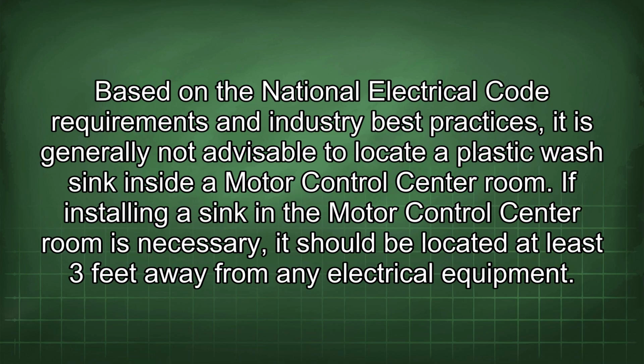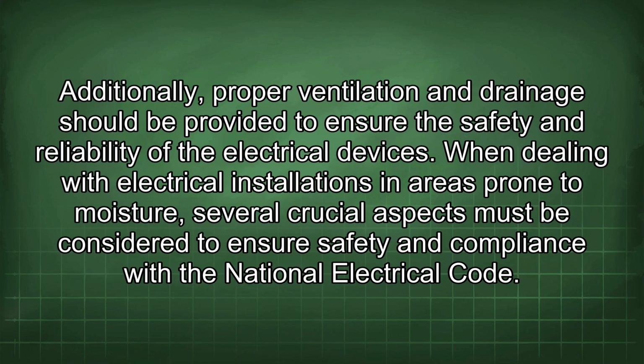Based on the National Electrical Code requirements and industry best practices, it is generally not advisable to locate a plastic wash sink inside a motor control center room. If installing a sink in the motor control center room is necessary, it should be located at least 3 feet away from any electrical equipment. Additionally, proper ventilation and drainage should be provided to ensure the safety and reliability of the electrical devices.